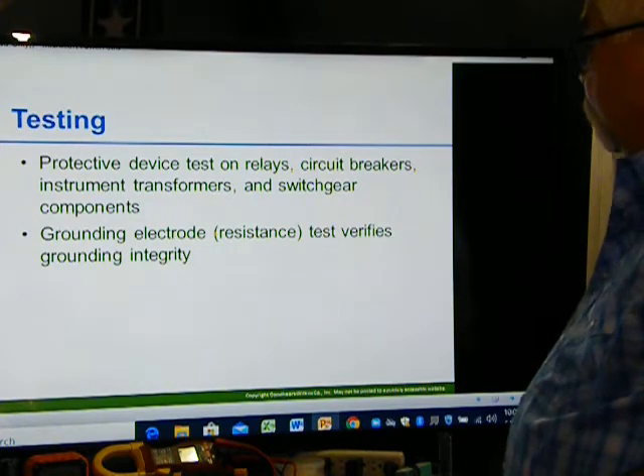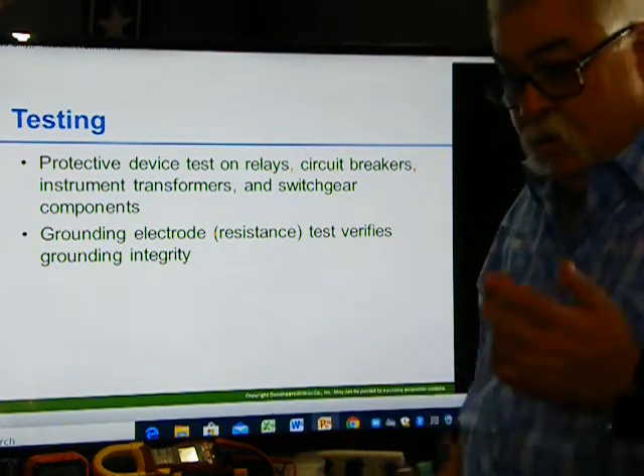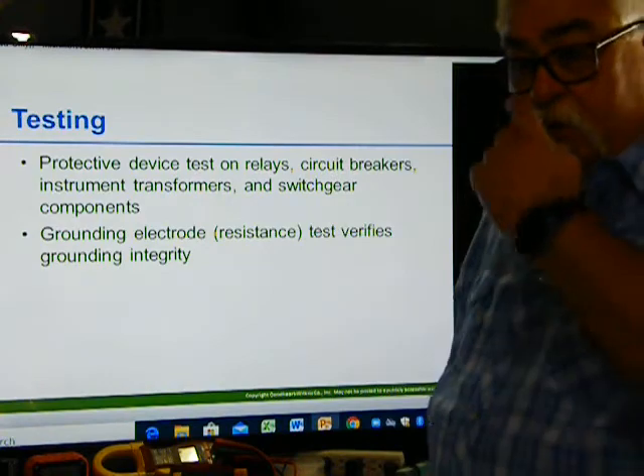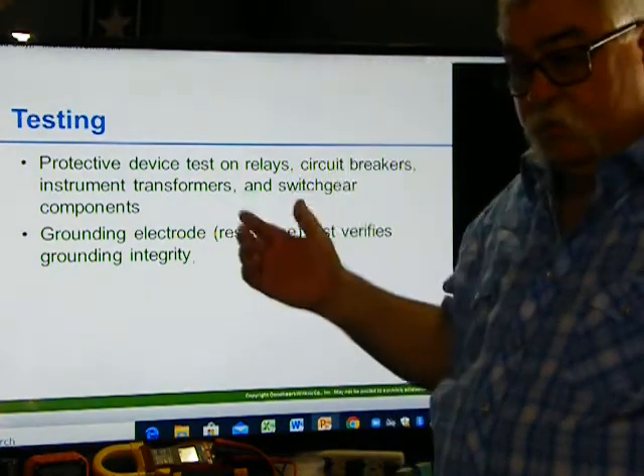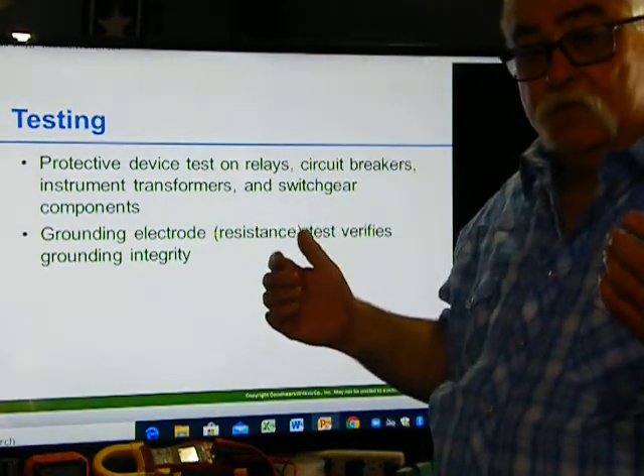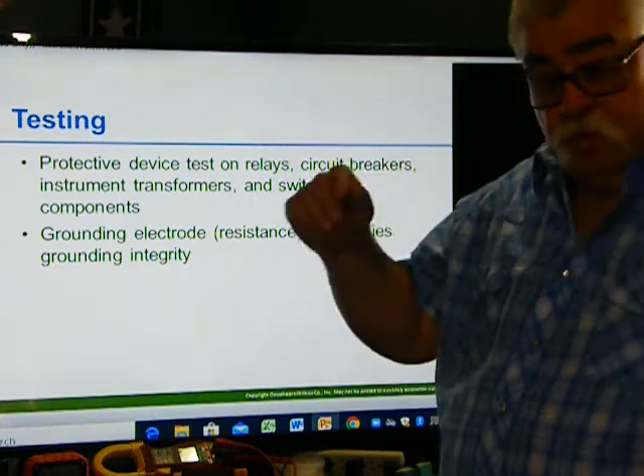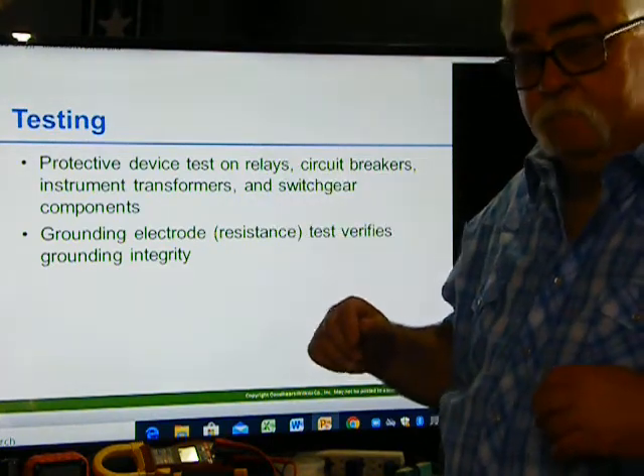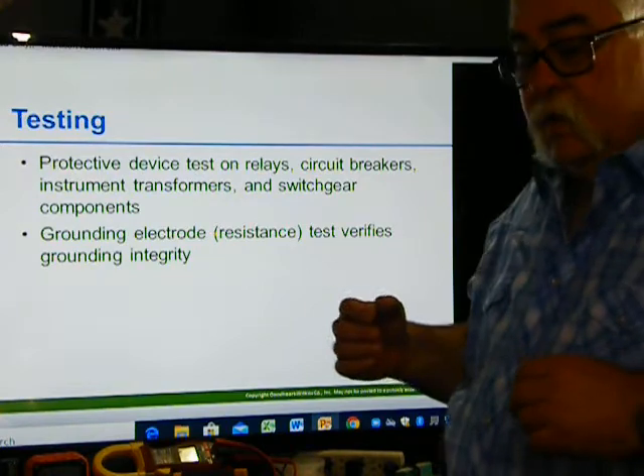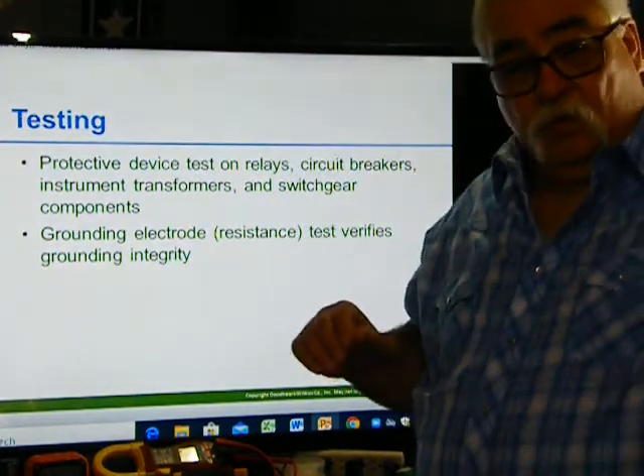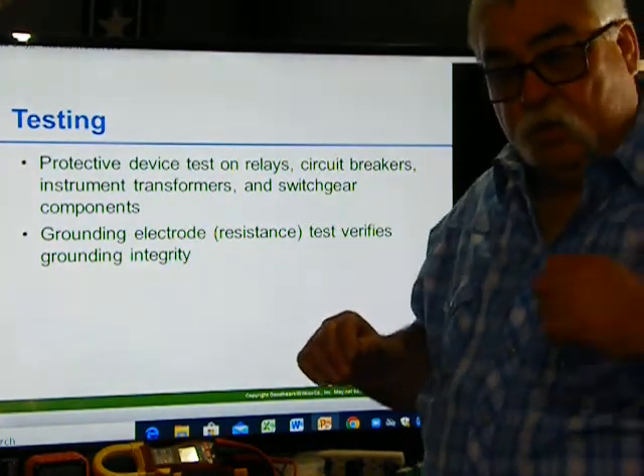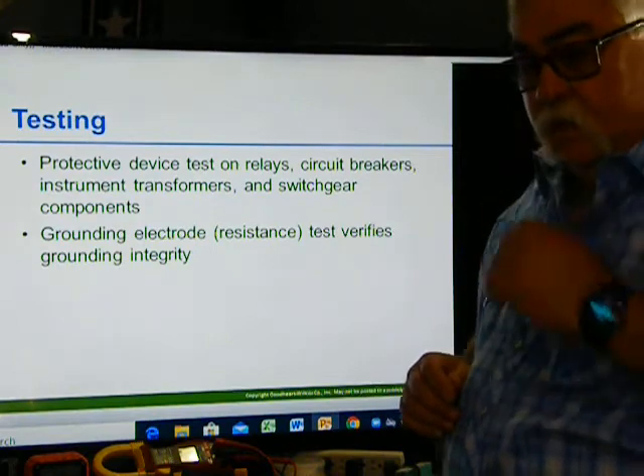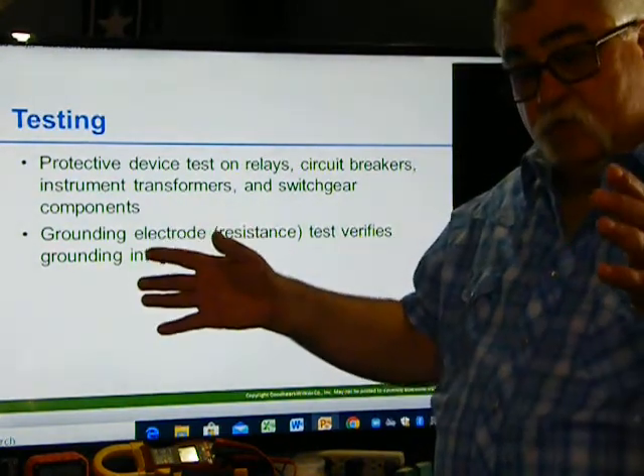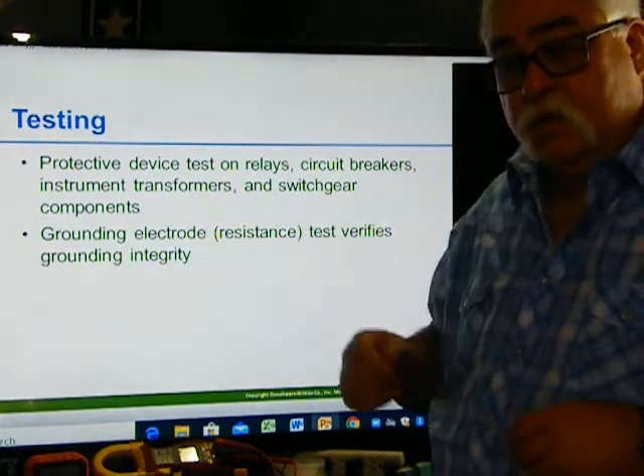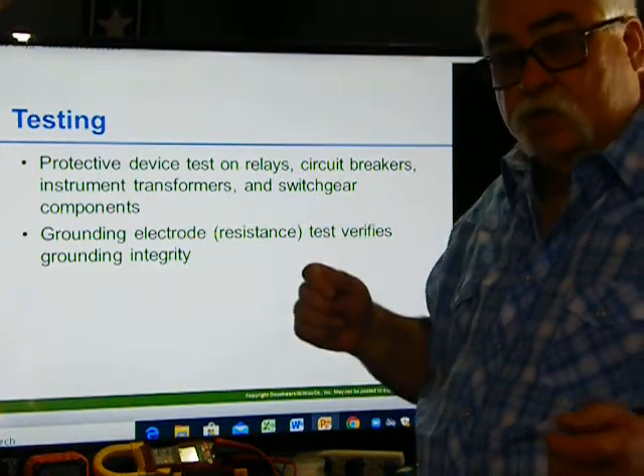Transformers and switchgear components, making sure everything's bolted down. If we had a planned outage, okay, like we had some dry type transformers and we cleaned them up once a year. So we go in there, we turn power off on the high voltage side, because we controlled our own high voltage. So we go in there and go to the plant, switch off the switchgear, and then isolate the transformer. Go in there and discharge it with a piece of wire to ground. So we discharge the transformer, and then go in there and clean it.